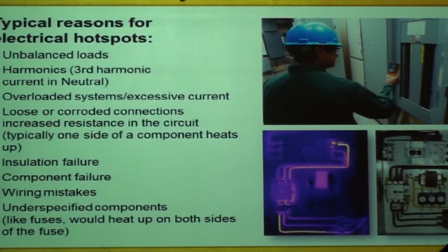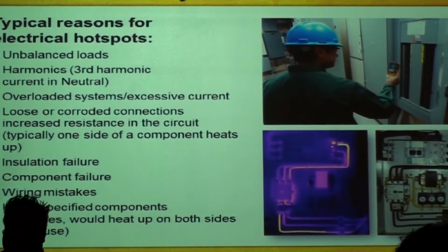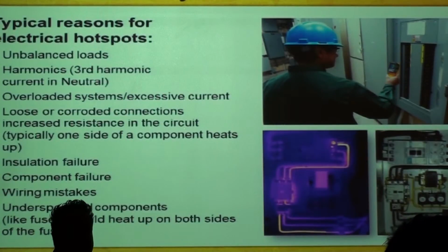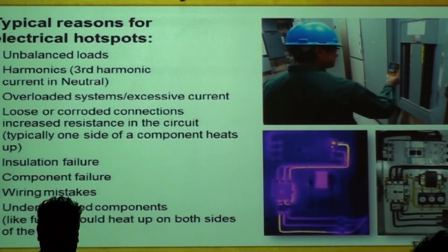Because the customer blew the fuse, he didn't have the patience and the time to wait to call the agent to send a replacement fuse. He wanted to get his job done, so he did the next best thing. He just made a contact with the wire. That wire is under-specified. It's not going to help you if you have an overload condition, right? Those fuses are meant for your protection.